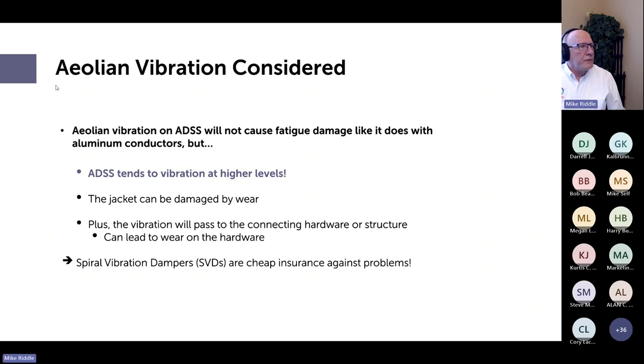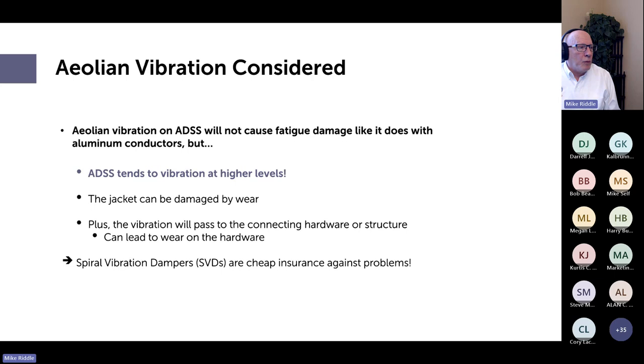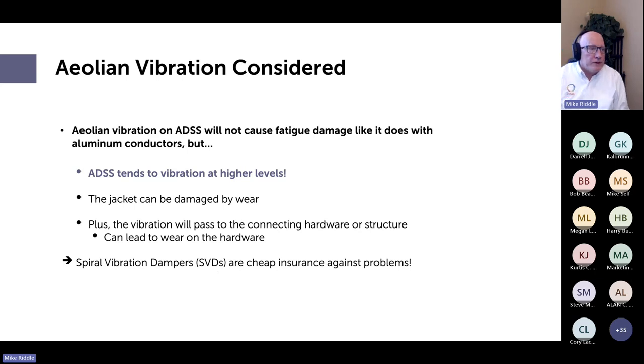Moving on to other accessories. Aeolian vibration is not likely to cause fatigue damage to ADSS cable itself — this contrasts significantly with aluminum-containing cables like ACSR or OPGW. However, ADSS does tend to vibrate at higher levels, and if the vibration causes the cable to rub against something, you can get jacket damage from wear. That vibration energy also passes through to connecting hardware or the structure, causing hardware wear too. I consider spiral vibration dampers to be cheap insurance and suggest you always use them.